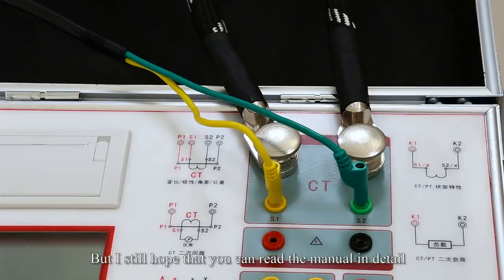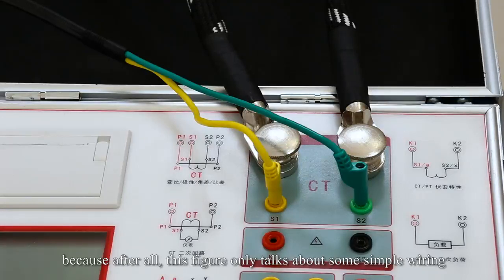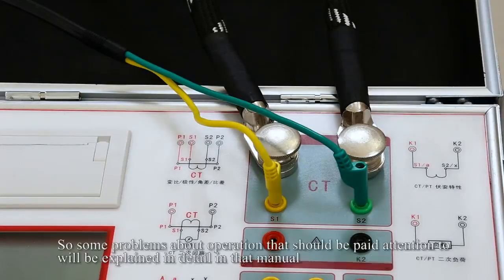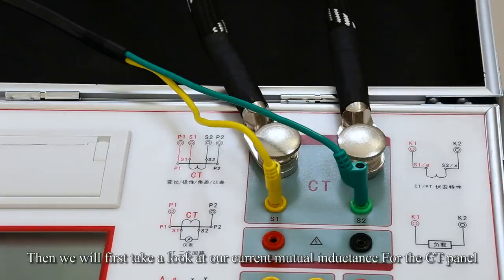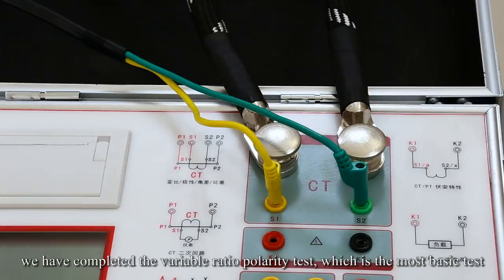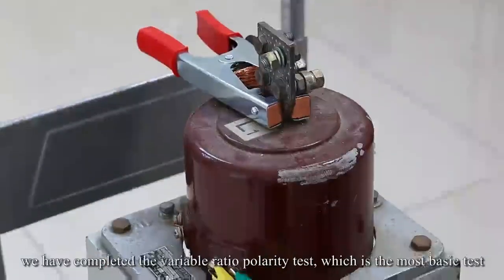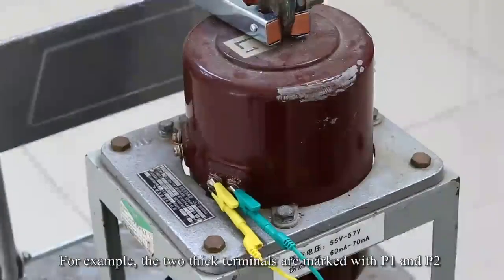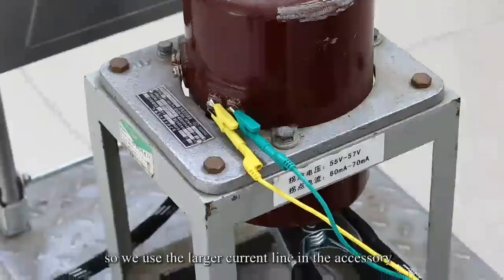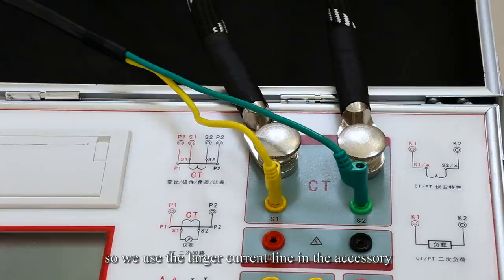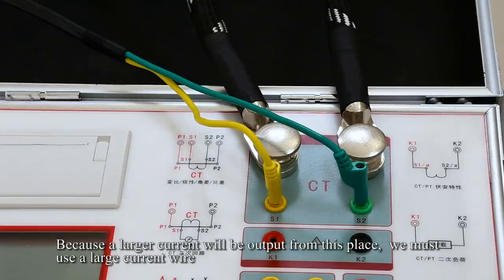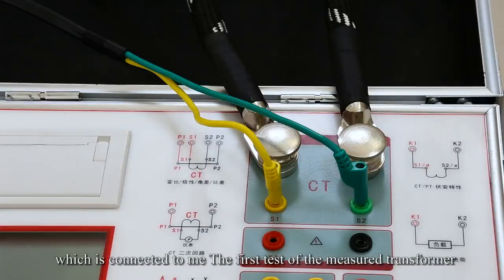But I still hope you can read the manual in detail, because the figure only shows simple wiring, and the points to pay attention to are explained in detail in the manual. Then we will start the formal operation. First we look at the current transformer CT panel, where we complete the ratio polarity test, which is the most basic test. The two thick terminals are marked P1 and P2, so we use the larger current line from the accessories, because a larger current is output from here. It is connected to the primary of the measured transformer.